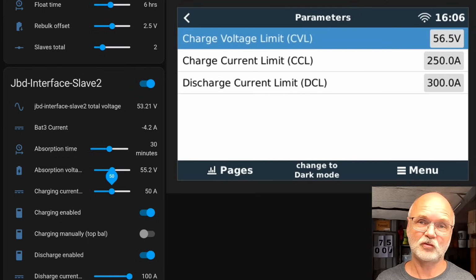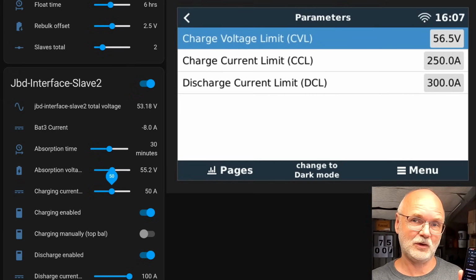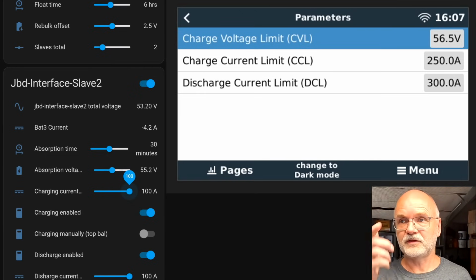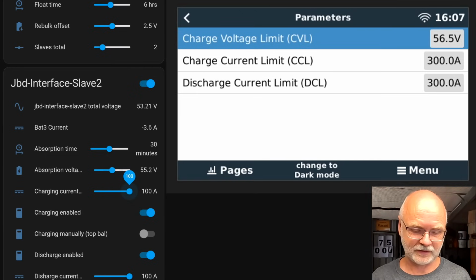This is nothing we can control, because the batteries are all in parallel, and depending on the internal resistance, state of charge, temperature, all this kind of stuff, they take as much current as they need. But we can tell the system to slow down. So if I change this back to 100, we will see it goes back to 300 amps as well.